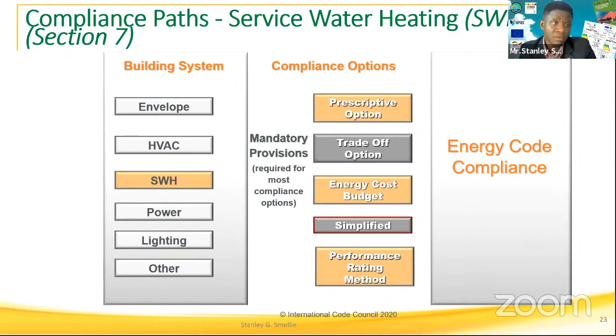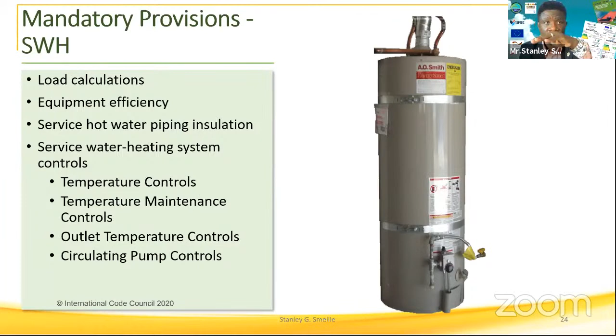And electric not only for human use or potable water use, but also, for example, a swimming pool or other purposes. In that case, the mandatory requirements of the ASHRAE standards tell you that you need load calculations, equipment efficiency data, and information on the piping and how it's insulated. We need to know information about the service water heating system and the controls available. By asking these questions, the code provides details in terms of what to look for, what the level should be, and how you can achieve the compliance you seek.